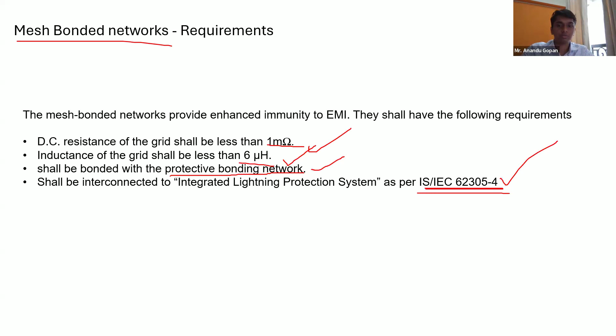So when you follow a mesh bonding system, the DC resistance between two adjacent points in a grid must be less than 1 milliohm. The inductance must be less than 6 microhenry. It should be connected to the protective bonding network, and it must be as per part 4 of 62305.